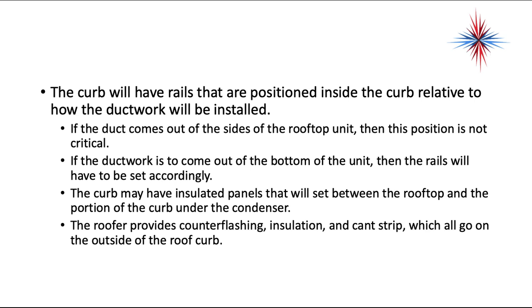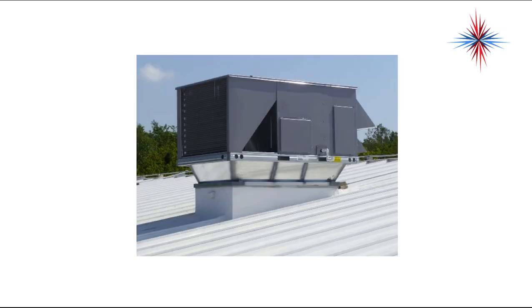The curb will have rails that are positioned inside the curb relative to how the ductwork will be installed. If the duct comes out of the side of the rooftop unit, then this position is not critical. If the ductwork comes out of the bottom of the unit, then the rails will have to be set accordingly. The curb may have insulated panels that will set between the rooftop and the portion of the curb under the condenser. The roofer provides counterflashing, insulation, and a nailer strip, which all go on the outside of the roof curb.